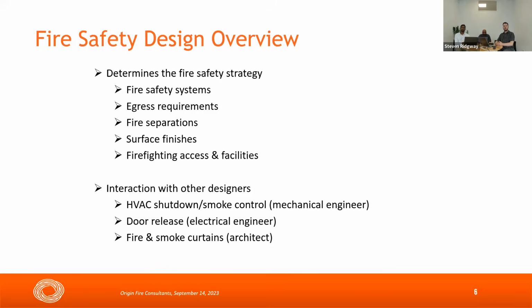So when we get into the fire safety design, this is covered in your fire report. The fire safety design determines the fire safety strategy. So we'll specify things like the fire safety systems that you need in the building, egress requirements, and what kind of fire separations you need, whether it's to protect life safety or to protect property, and we'll give you a rating that you need to achieve. I'll talk more about that later. I'll talk about surface finishes, which is about how flammable your wall, floor, and ceiling linings are. Too flammable, obviously, they're going to catch fire very quickly, and you can have quite a risk to occupants.